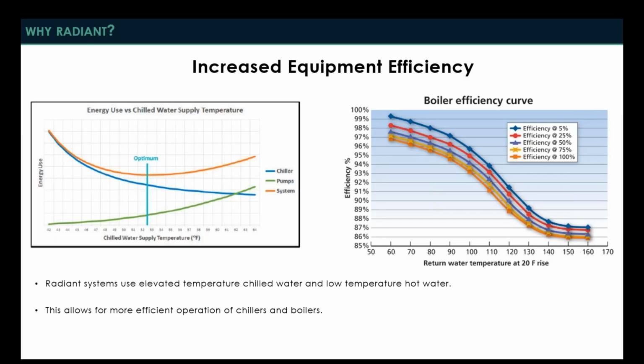So let's answer the question of why radiant? Why would I want to do this? Well, we already mentioned the idea of energy efficiency and how these types of systems can improve efficiency in a building. So it can improve the overall HVAC efficiency, but it can also specifically improve the efficiency of your cooling and heating plant. And the reason is that radiant systems are using what is called elevated temperature chilled water and low temperature hot water. So that's kind of a contradiction when we're talking about hot chilled water and cold hot water. But the idea is that the warmer the chilled water temperature is, the less energy it takes to produce that chilled water. And the converse is true on the hot water side.